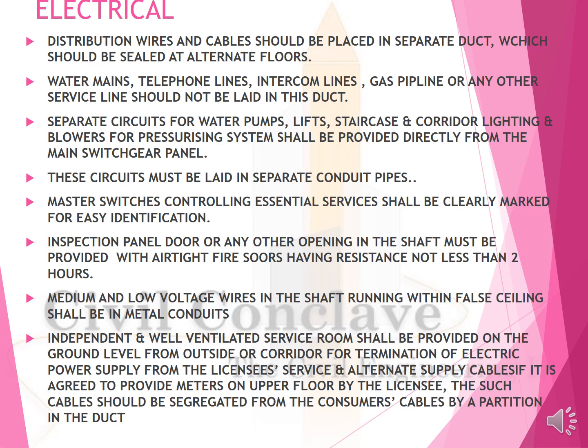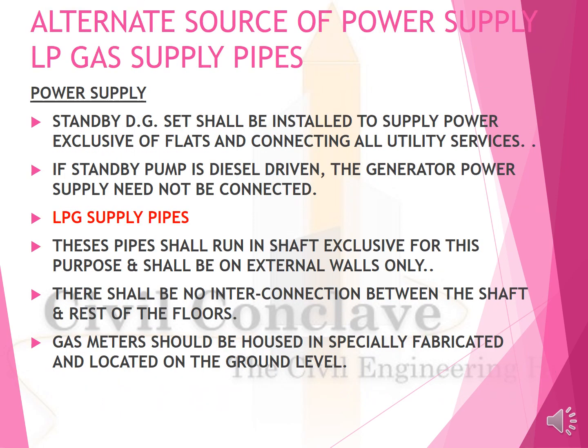Inspection panel, door or any other opening in the shaft must be provided with an airtight fire resistance of not less than 2 hours. Medium and low voltage wires in the shaft running within the false ceiling shall be of metal conduits. Alternative source of power supply, LPG gas supply lines, etc. Power supply. Standby DG set shall be installed to supply power exclusive of flats and connecting all utility services. If standby pump is diesel driven, the generator power need not be connected.